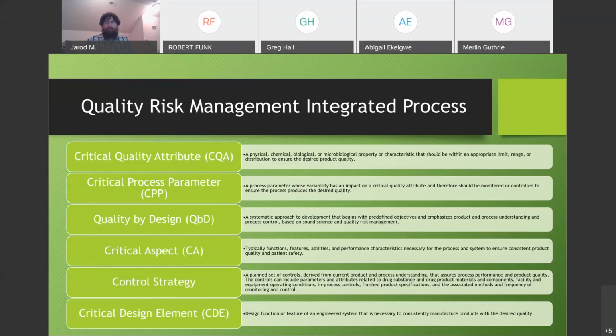Some language around the quality risk management process: a critical quality attribute is a physical, chemical, biological, or microbiological property, a characteristic that should be within an appropriate limit, range, or distribution to ensure desired product quality. A critical process parameter is a parameter whose variability has an impact on the critical quality attribute and therefore should be monitored or controlled to ensure the process provides desired quality. Quality by design is a systematic approach to development that begins with predefined objectives and emphasizes product and process understanding and process control, based on sound science and quality risk management.